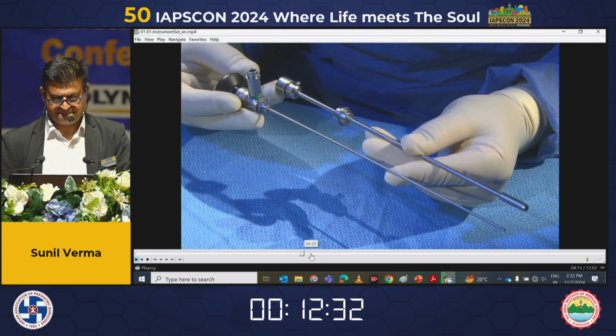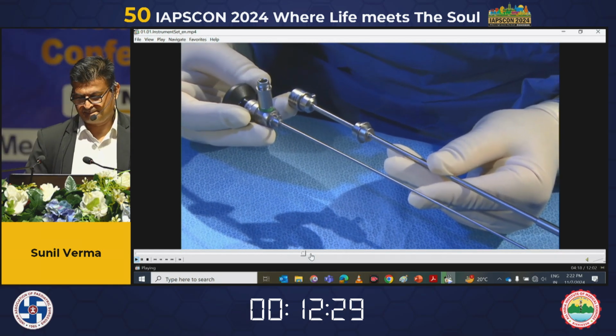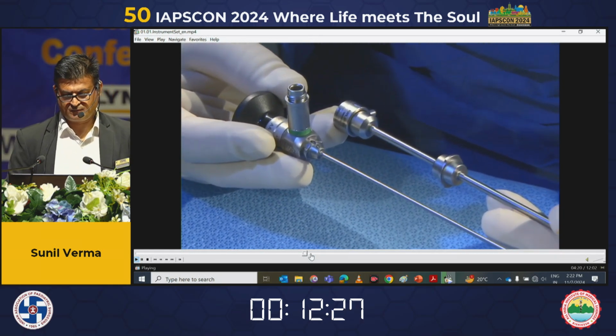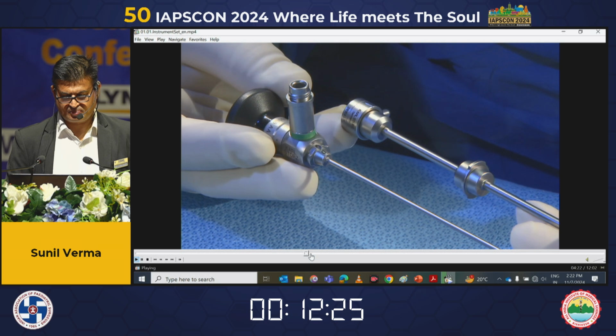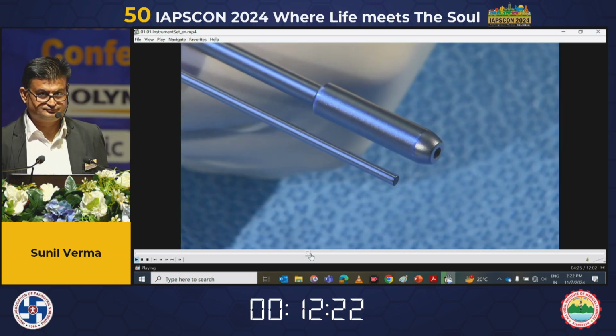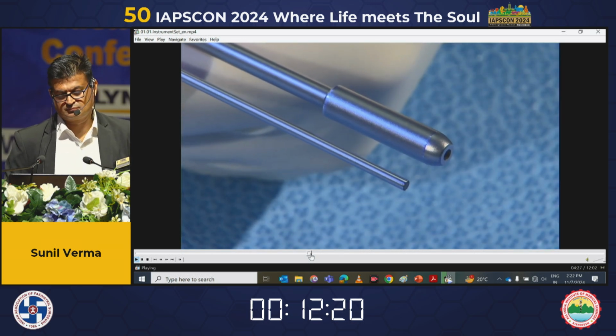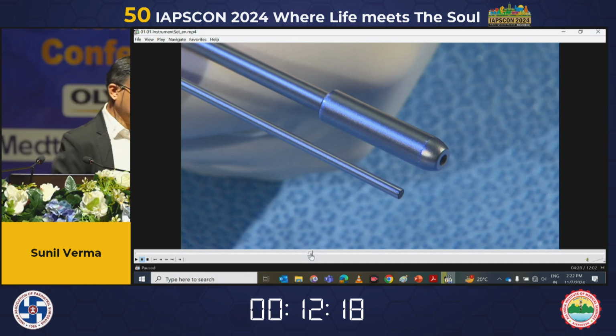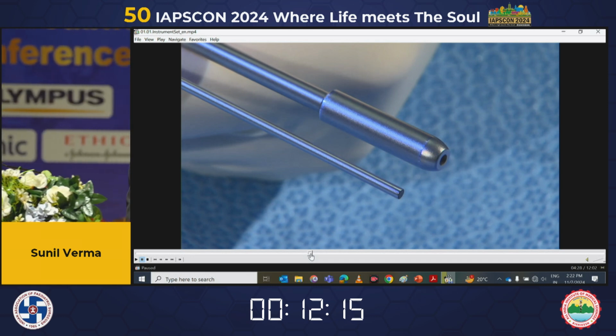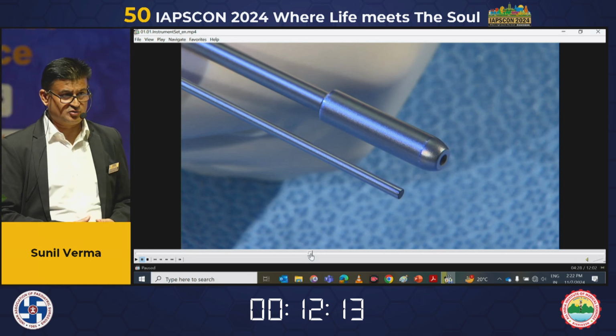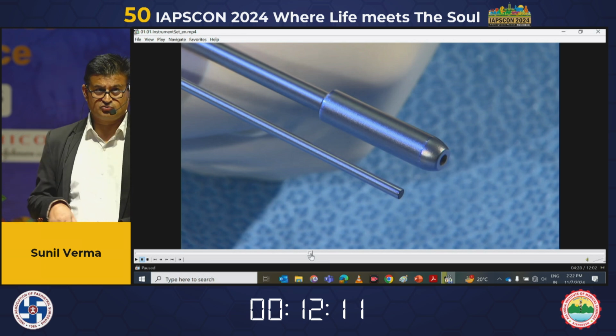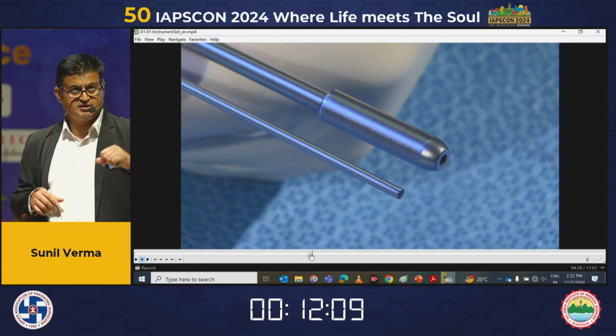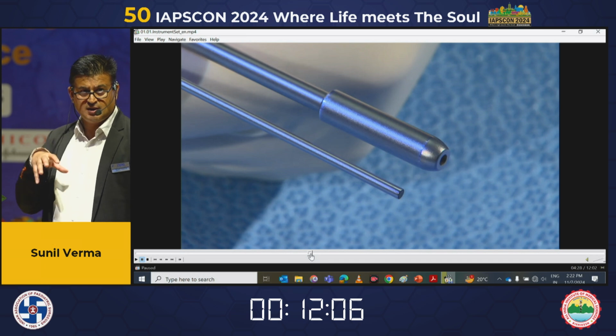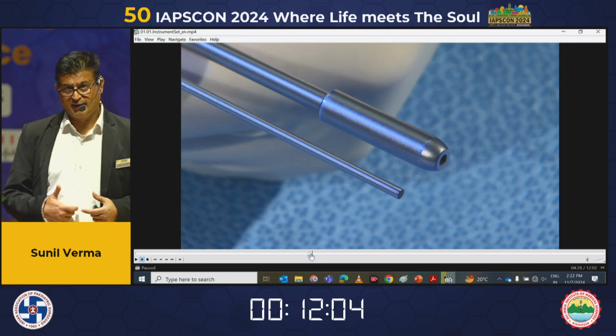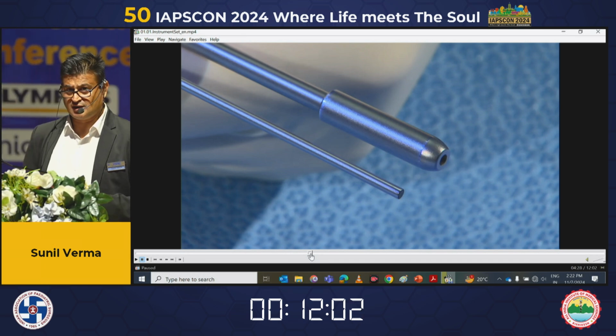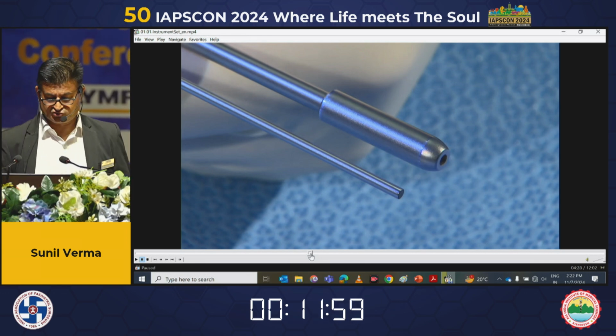An optical obturator is available for the atraumatic insertion of the endoscope sheath through narrow openings, such as a small foramen of Monro. This comprises a drilled open obturator into which a thin 0-degree endoscope is inserted. Sometimes the foramen of Monro is not dilated enough, so rather than taking the risk of doing a foraminoplasty, you can use this visual obturator. Since it has a hole with a lens, you can put a 2 mm scope, connect it with the camera, and even enter under vision into the lateral ventricle, as you do with some of the trocars in laparoscopic procedures.